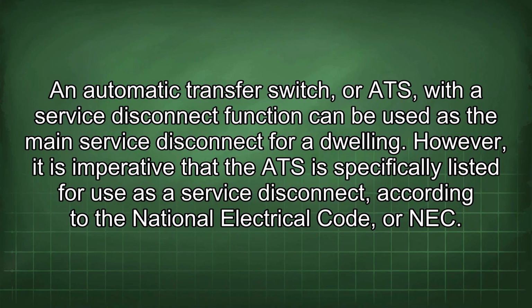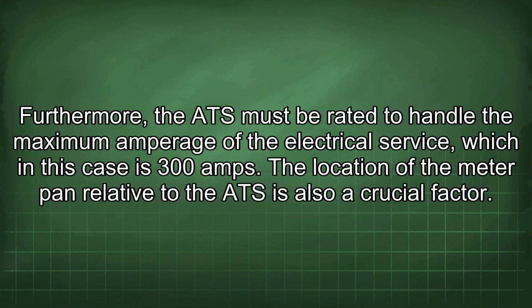An automatic transfer switch, or ATS, with a service disconnect function can be used as the main service disconnect for a dwelling. However, it is imperative that the ATS is specifically listed for use as a service disconnect according to the National Electrical Code, or NEC. Furthermore, the ATS must be rated to handle the maximum amperage of the electrical service, which in this case is 300 amps. The location of the meter pan relative to the ATS is also a crucial factor.